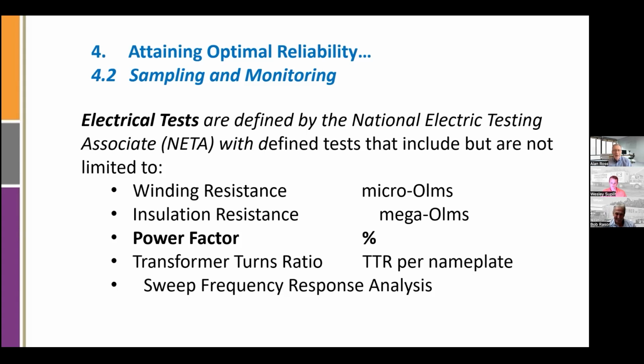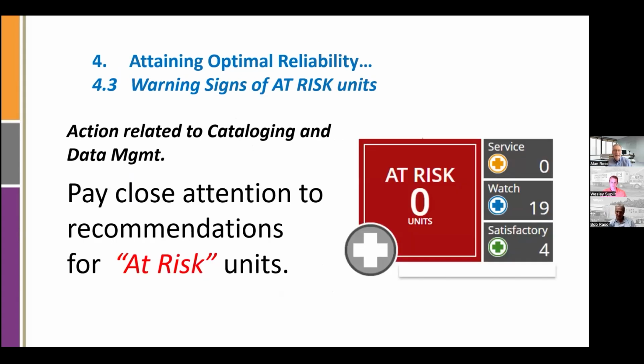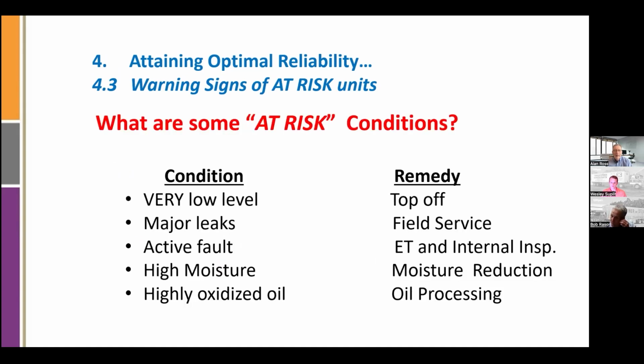All right. So here's your at-risk detail. Pay close attention to these. When the level is very, very low, the radiator tubes or the cooling system can be compromised to where the transformer is overheated. Major leaks, you're looking at moisture ingress and problems. If you have an active fault showing up in your gas and oil analysis, definitely recommend electrical testing. You're looking for the high temperature gases like acetylene and ethylene.